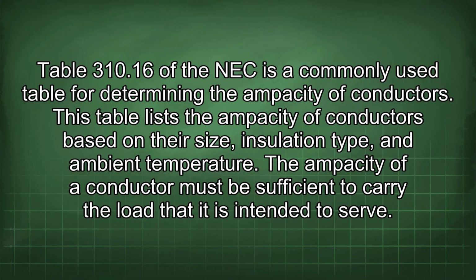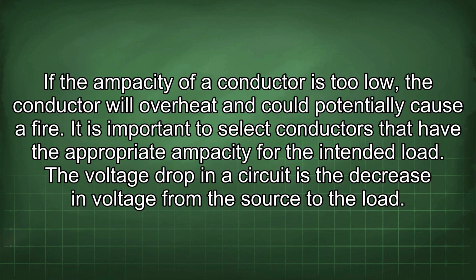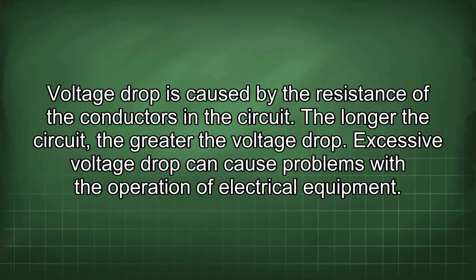The ampacity of a conductor must be sufficient to carry the load that it is intended to serve. If the ampacity of a conductor is too low, the conductor will overheat and could potentially cause a fire. It is important to select conductors that have the appropriate ampacity for the intended load. The voltage drop in a circuit is the decrease in voltage from the source to the load. Voltage drop is caused by the resistance of the conductors in the circuit. The longer the circuit, the greater the voltage drop.